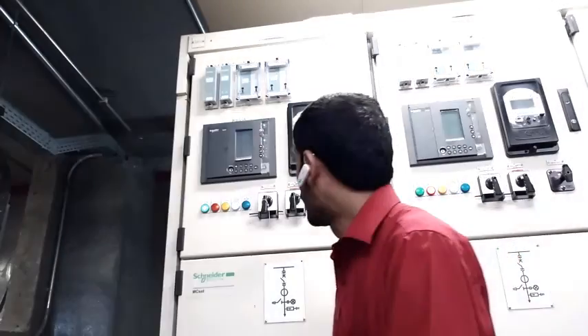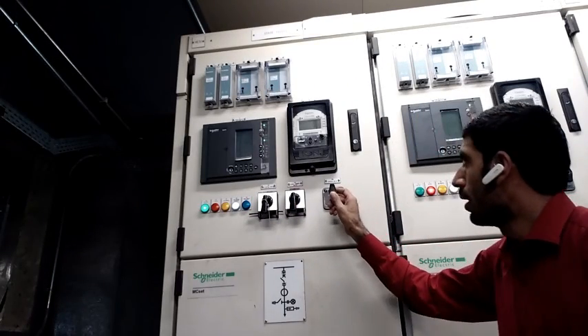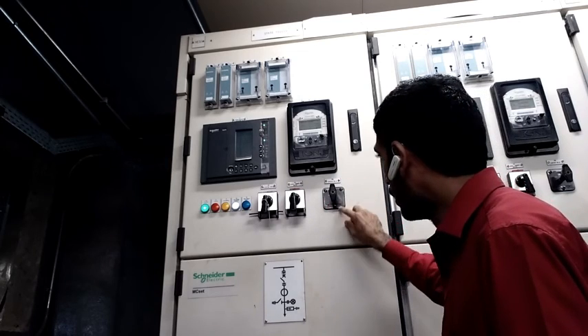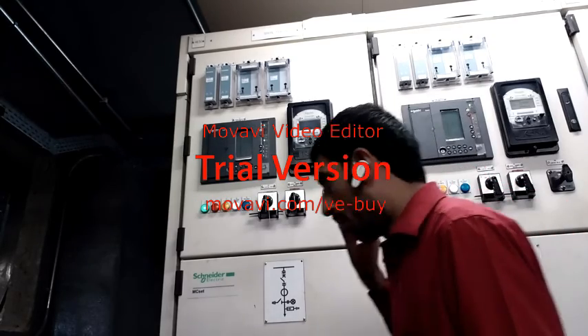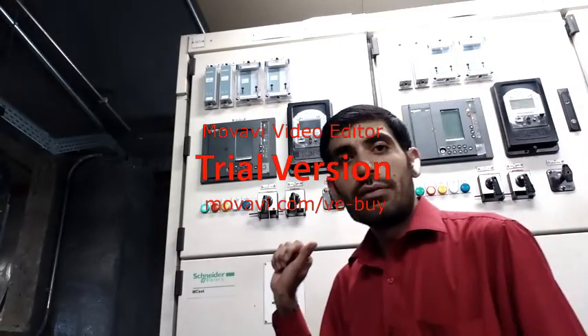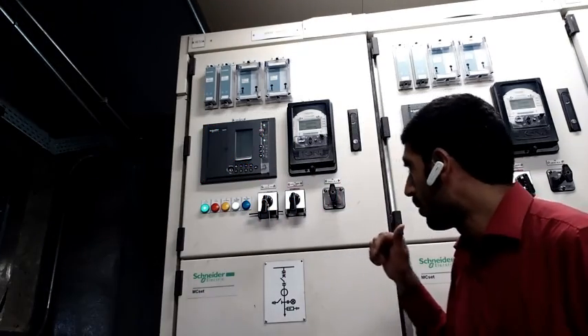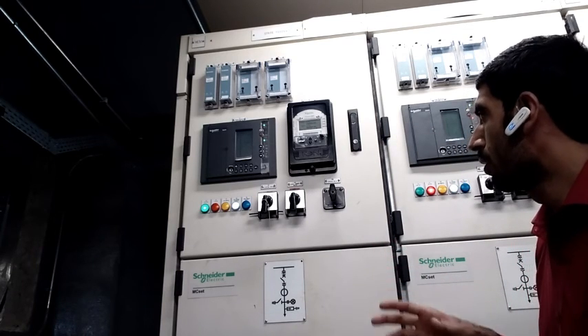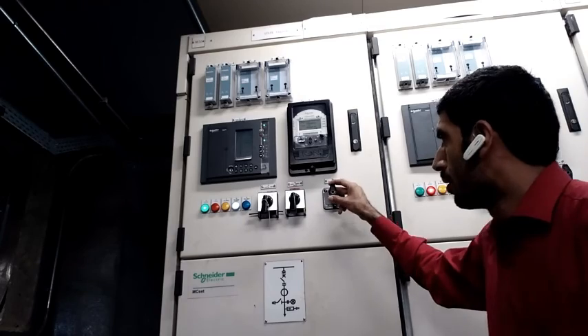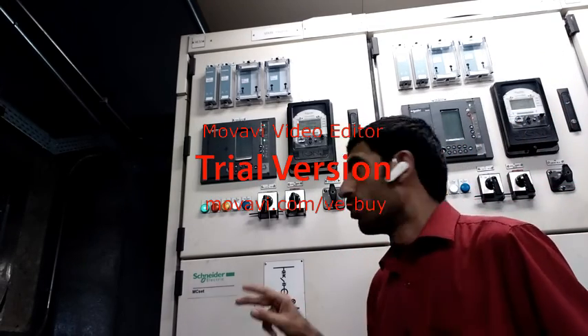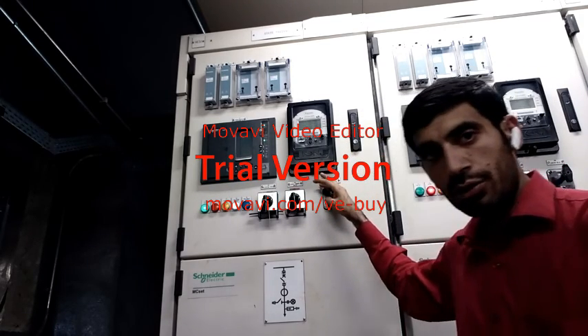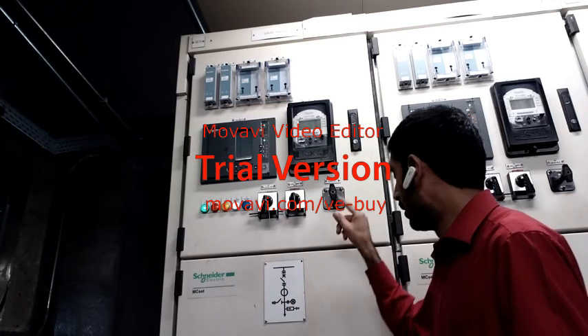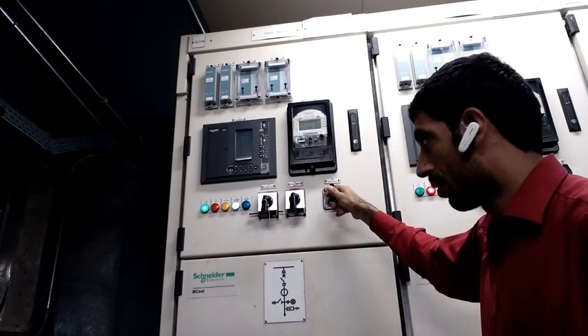And the next thing is the lockout relay. This lockout relay, made by GE, we use for the safety of breaker reclosing. If anything happens in our system or outside it, for example a short circuit or earth fault, this relay will trip and hold in the trip condition. You cannot close your breaker until you reset this relay. When you reset this relay, you can reclose your breaker. This relay is used for safety protection of the breaker.